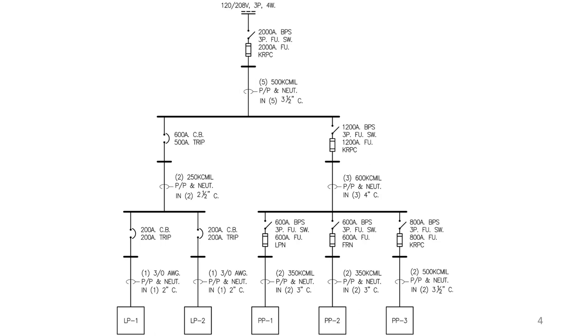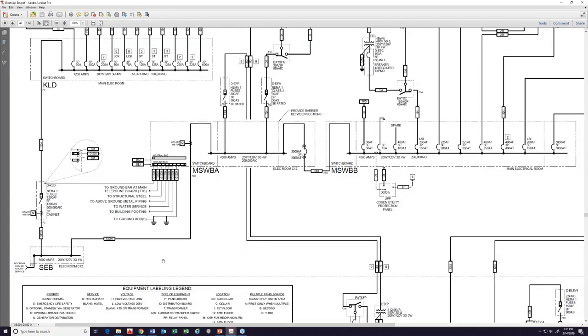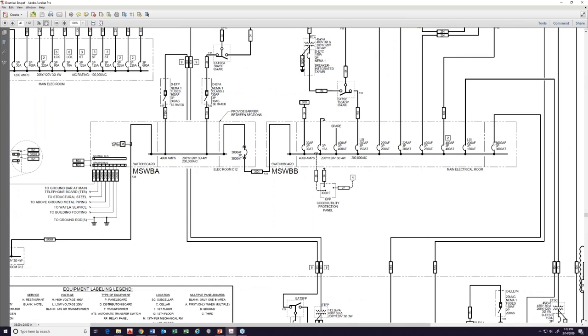So when most engineers' drawings come out, and we get a lot of those where we will do studies, I will show you such examples. This is an example of a consultant drawing. It doesn't matter who it is, how old it is, and where the job is, but it's a point of making a reference. I have a utility service coming in. I hope you guys can follow my mouse, my little hand, coming in to feed a switchboard. And I've got some lines going out to feed the fire alarm system, the fire pump. And then I have a 3,000 amp circuit breaker feeding a distribution. However, over here at the end, I've got another 3,000 amp circuit breaker feeding a step-up transformer, which is going to feed some mechanical equipment.